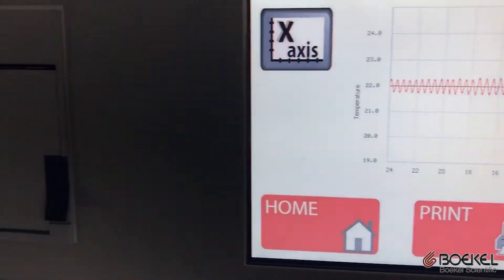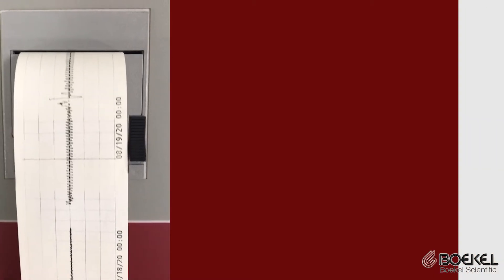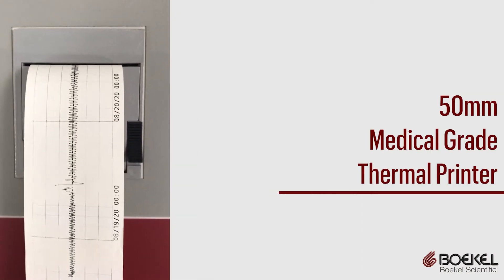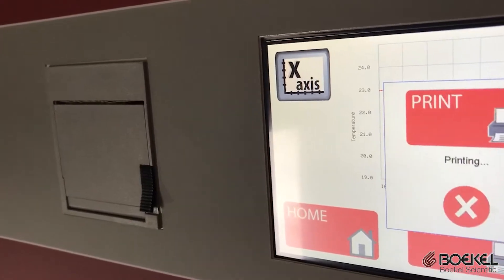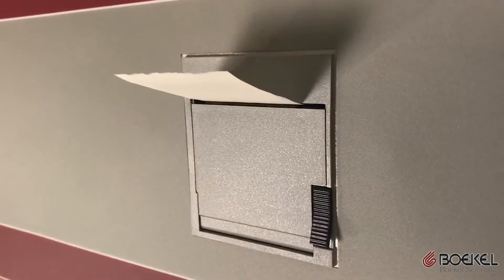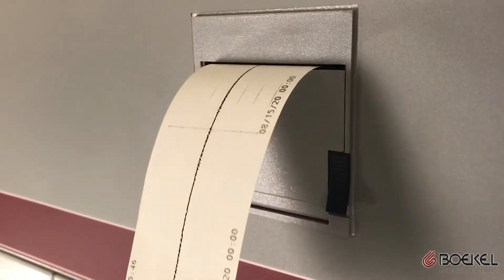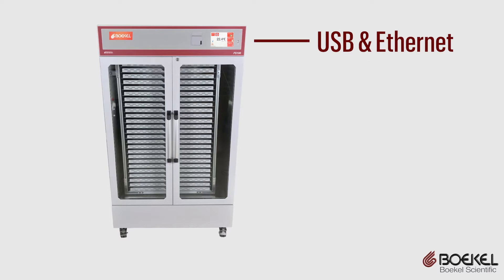Boekel Scientific was also the first to use a thermal printer in the platelet incubator for temperature and alarm reporting. Say goodbye to old-school chart recorders with monthly service requirements. The thermal printers print information on demand and do not require regular service. Temperature data can also be downloaded via USB or Ethernet connection.